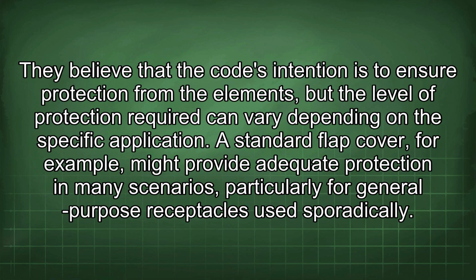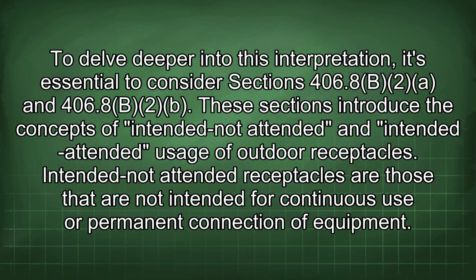They believe that the code's intention is to ensure protection from the elements, but the level of protection required can vary depending on the specific application. A standard flap cover, for example, might provide adequate protection in many scenarios, particularly for general-purpose receptacles used sporadically. To delve deeper into this interpretation, it's essential to consider sections 406.8(B)(2)(a) and 406.8(B)(2)(b). These sections introduce the concepts of intended not attended and intended attended usage of outdoor receptacles.